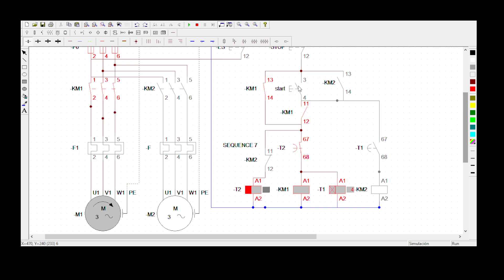When the start button is pressed, Motor 1 must start rotating - and we can see Motor 1 is rotating. The timer is energized and counting. You can check - it's on three, then on two. After it finishes counting for 10 seconds, you can then start Motor 2 using the very same start button.